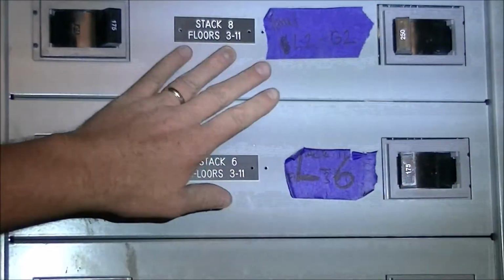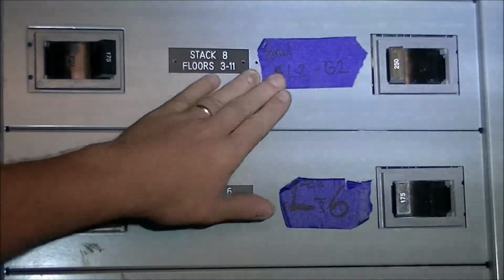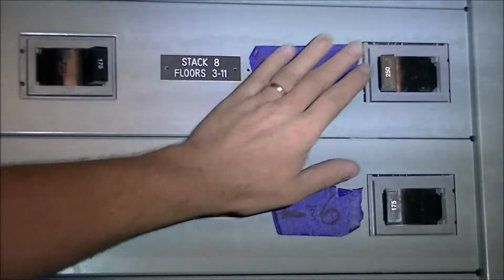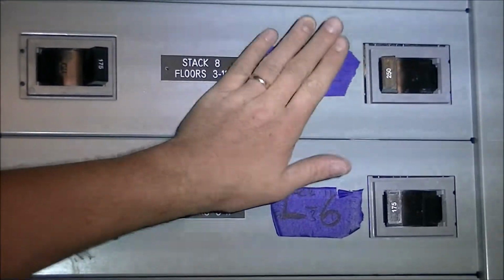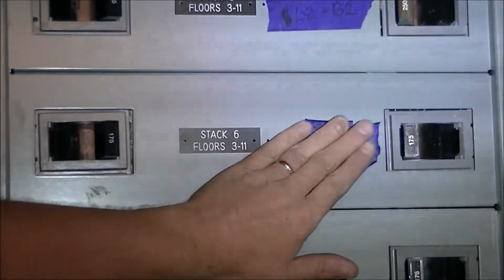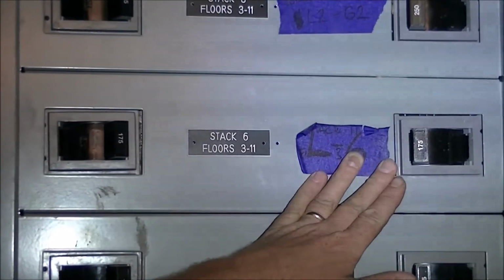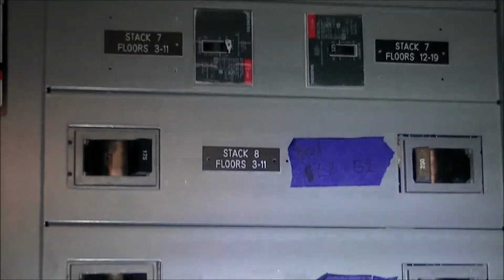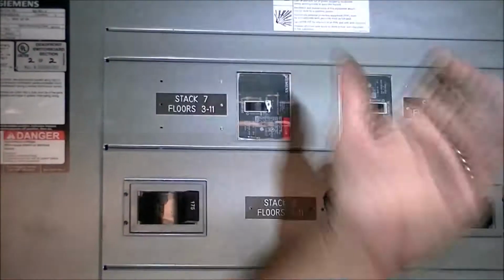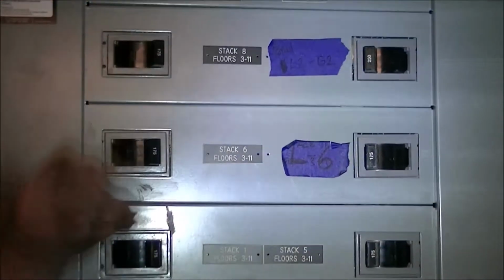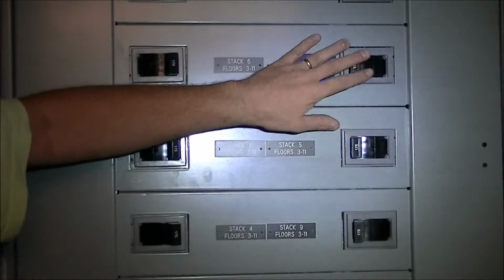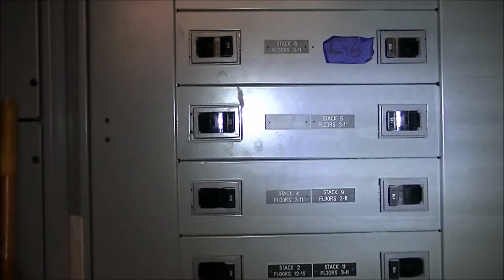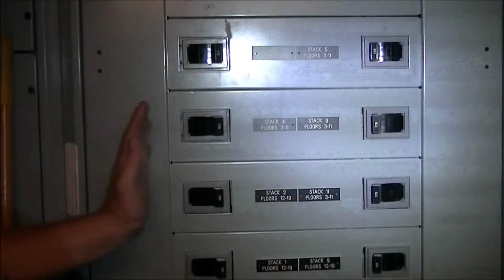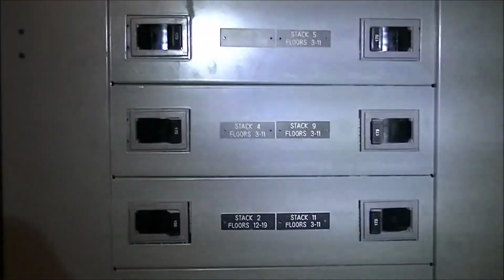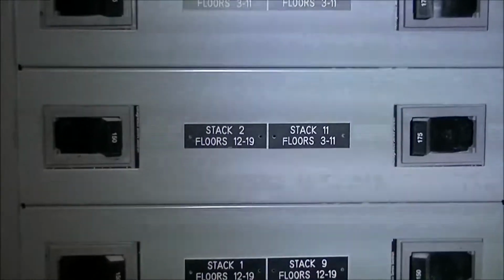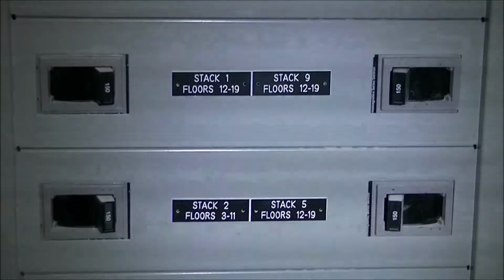Also coming out of this panel, you've got panel L2, where we've just come from. That's fed out of here, so if you lose the entire panel on L2, that's out of this one. We've got panel L6, on the 6th floor utility closet, also fed out of here. That also feeds panel L13, so both of those panels are out of here, but 13 is a sub-panel of 6, we'll get to that when we get up there. But again, this does all of your tenant space, all your tenant units. So if you ever lose an entire stack, you know you need to come down here.